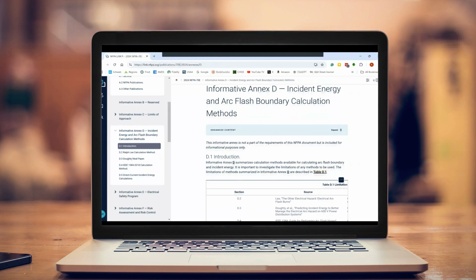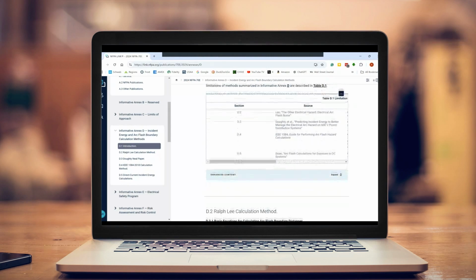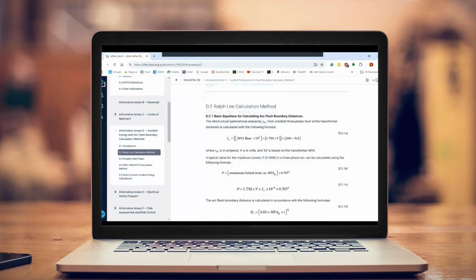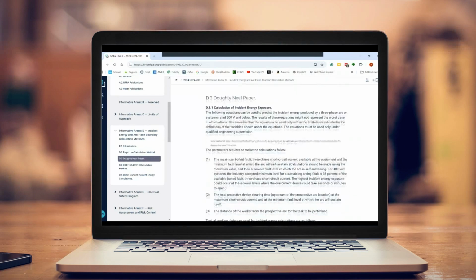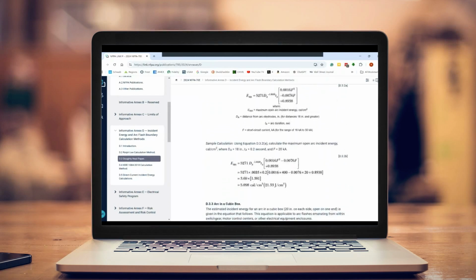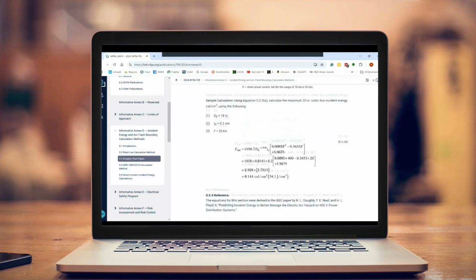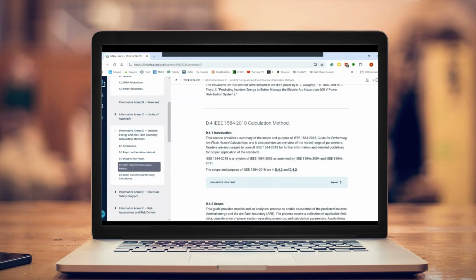So NFPA 70E gives you the rules, but the annexes give you a way to comply with those rules in real-world situations. When you're out in the field testing circuit breakers, transformers, cables, you have to follow the rules and comply with the standards. The informative annex gives you supplemental materials to do all that, and to do it well, and most importantly, to do it safely. So check out those informative annexes, read NFPA 70E, read the NETA testing standards, and before you work on it, test before touch.